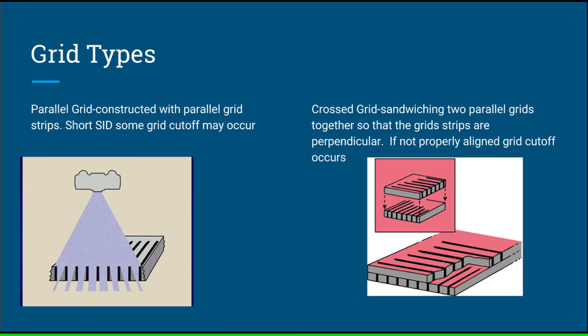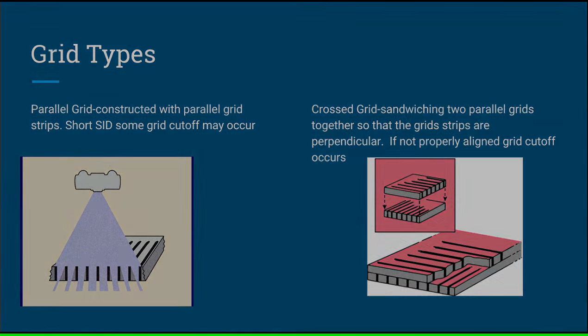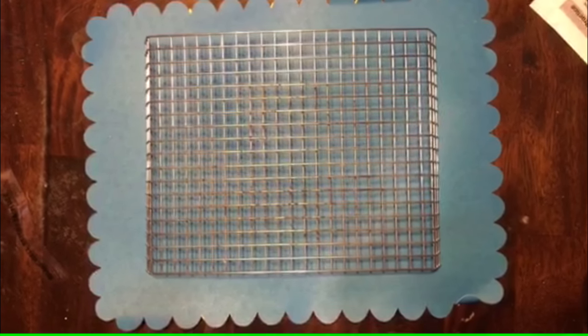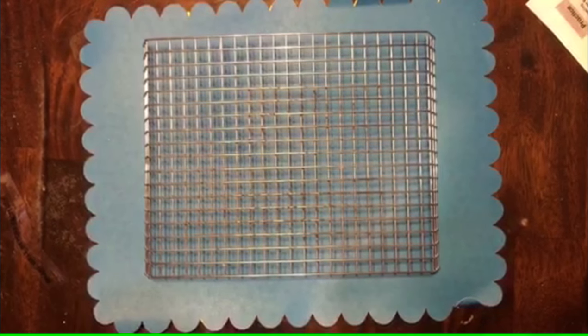Grid types: The parallel grid is constructed with parallel grid strips. With a short SID, some grid cutoff may occur. The cross grid is a sandwiching of two parallel grids together so that the grid strips are perpendicular; if not properly aligned, grid cutoff occurs as well. In this demonstration, the small cooling rack represents the radiographic grid. Notice how the grid only allows scatter radiation — represented by the silly string — to get through if it travels in the same angle as the holes of the rack, or the interspace material of a grid, while other scatter is prevented from going through by the radiopaque material of the grid strips.